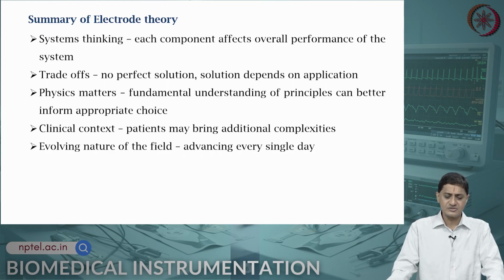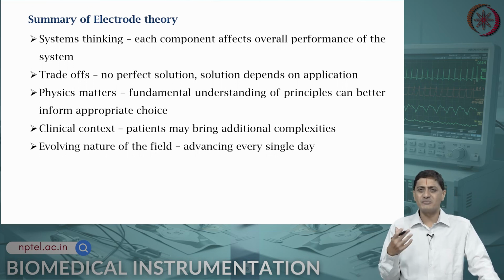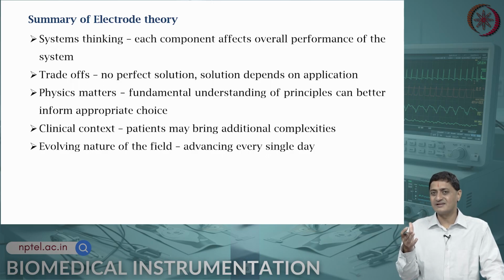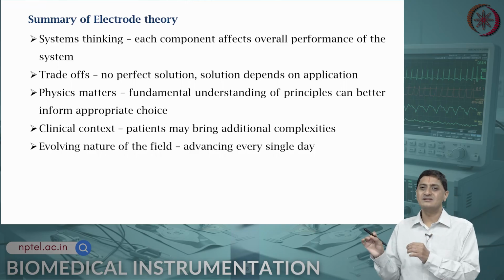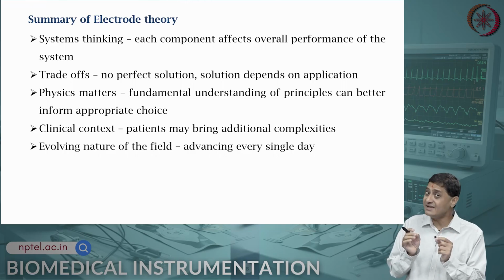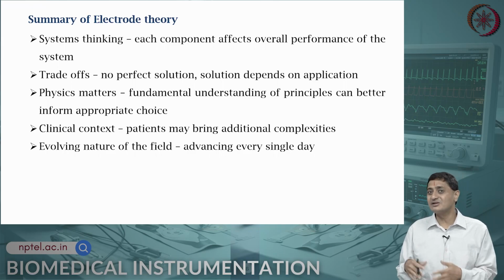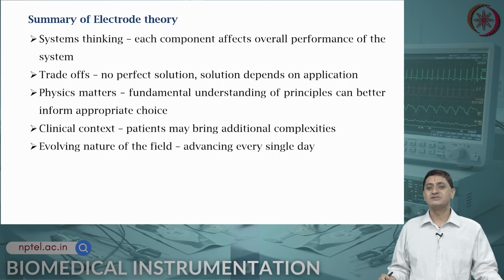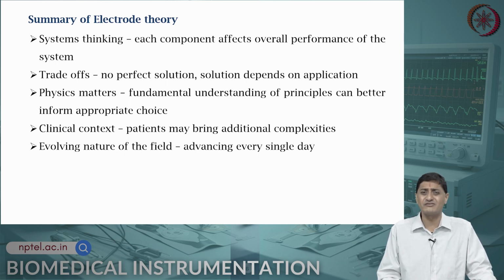Critically, it is important for us to recognize that each component affects the overall performance of the system. We need to learn that systems thinking: from the skin to the recording system, each component in that lead wire, whether you are soldering or welding, whether the metal and the lead wire are of the same type of metal or different types of metal, all these things matter. So, each component affects the overall performance of the system. There are trade-offs. There is no such thing as a perfect solution. The solution that you want depends on the particular application of interest.